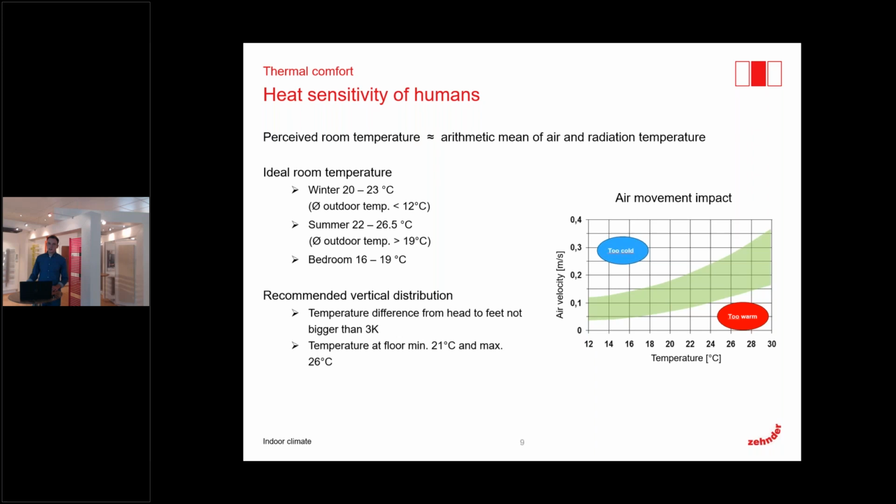And also, we like to have a vertical temperature distribution, have it warm in the area of our feet and a little bit cooler in the area of our head. And this temperature difference should not exceed 3 Kelvin.